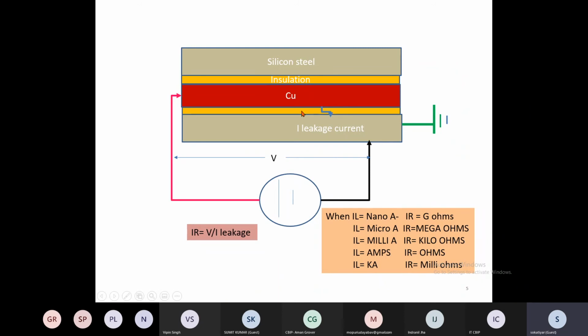Now, when the insulation is perfectly good, the leakage current is flowing in nanoamperes, and we say the IR value of the insulation is in gigaohms. If the leakage current increases from nanoampere to microampere, we say the IR value is in megaohms. If the leakage current increases to milliampere, we can say the IR value of the insulation is in kiloohms. And if the leakage current is in amperes, the IR value is in ohms. And if the insulation value decreases to milliohms, we say the leakage current goes to kiloampere.